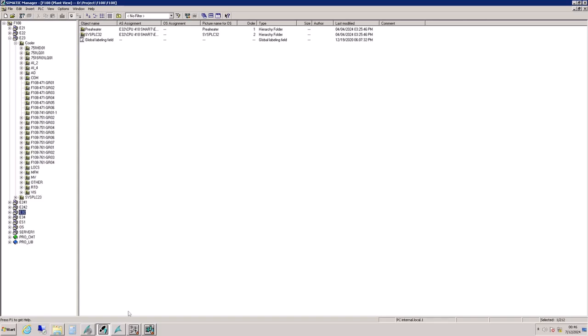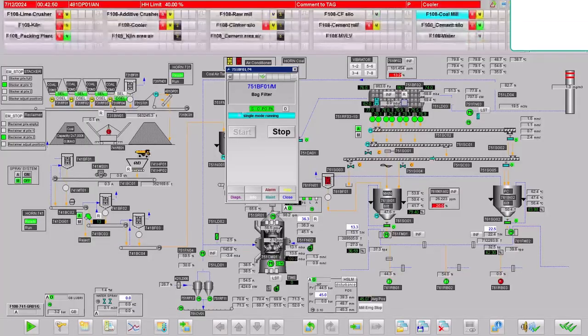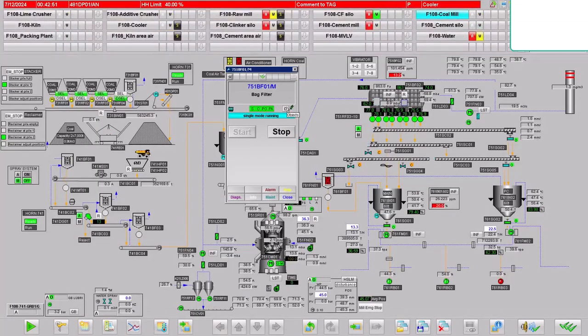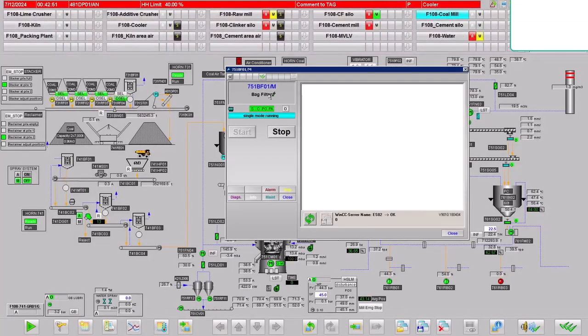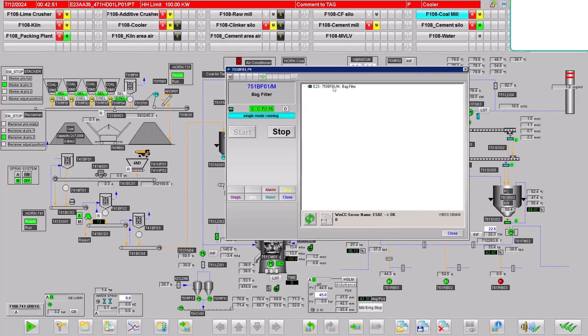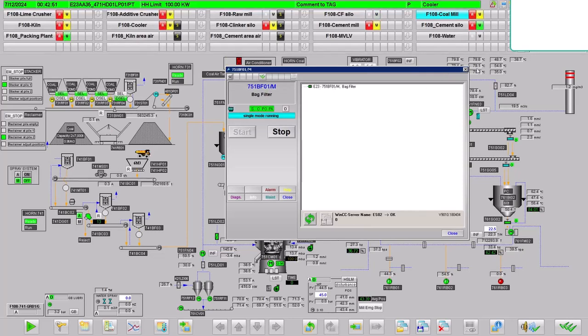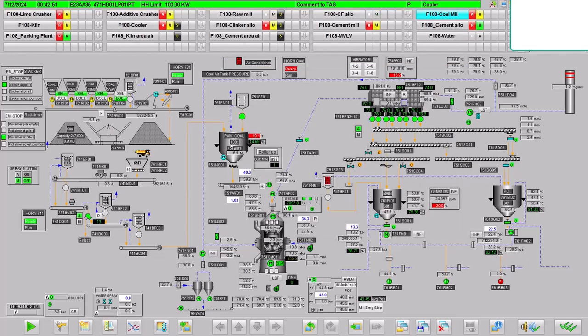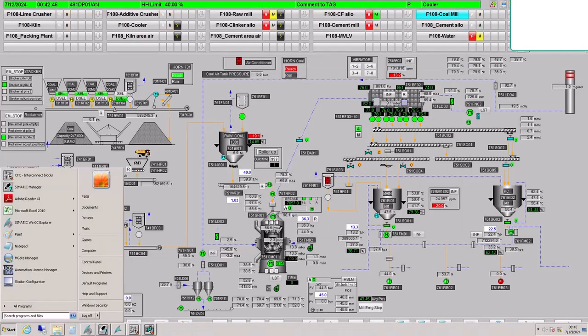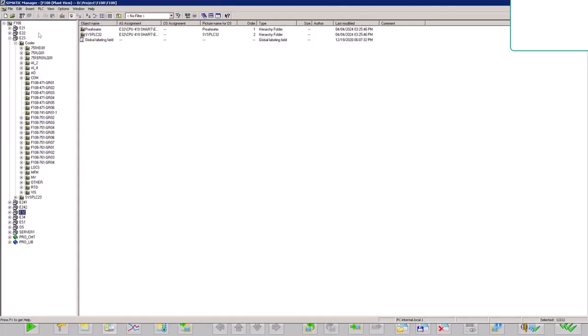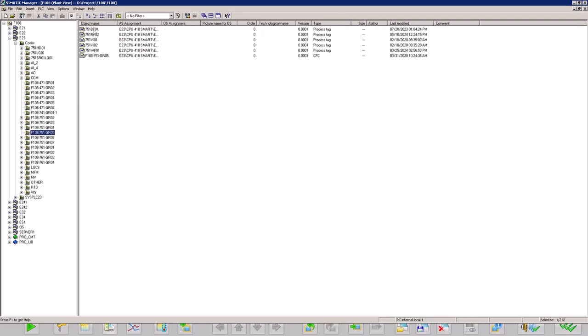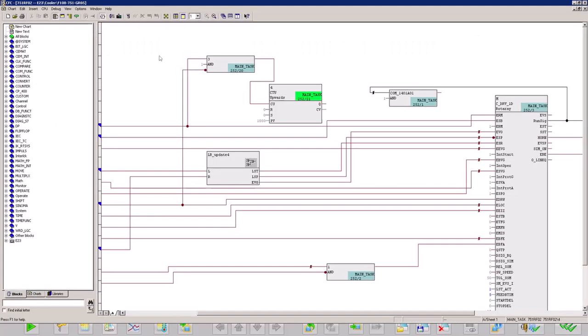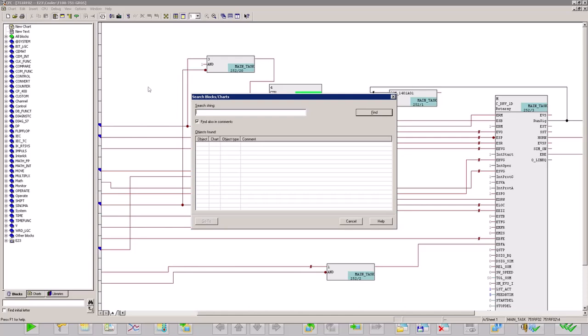The entire plant has been divided into various PLCs. So over here you can see 751 BF01 is the tag of the equipment and E23 is the PLC where it resides. I will click on any CFC chart in E23 PLC and I will press Ctrl+F, 751 BF01, I will click and find it.